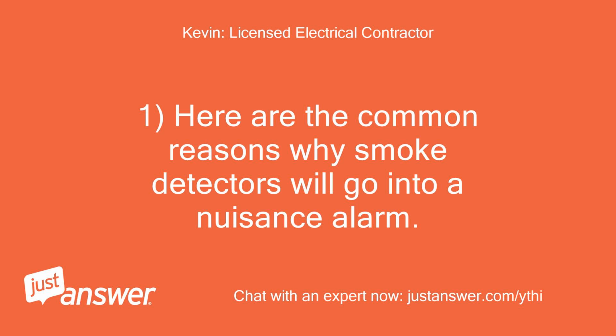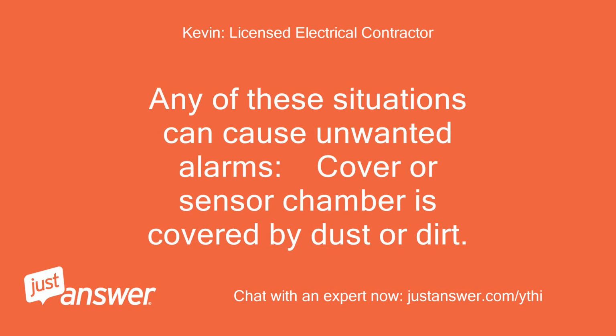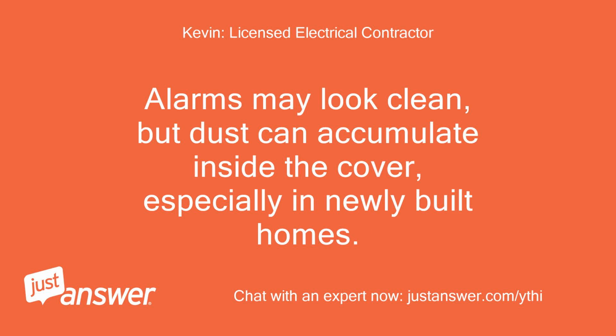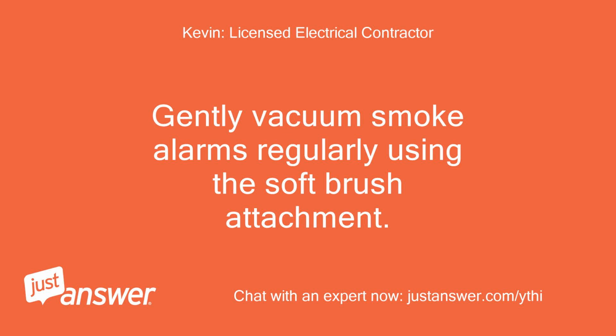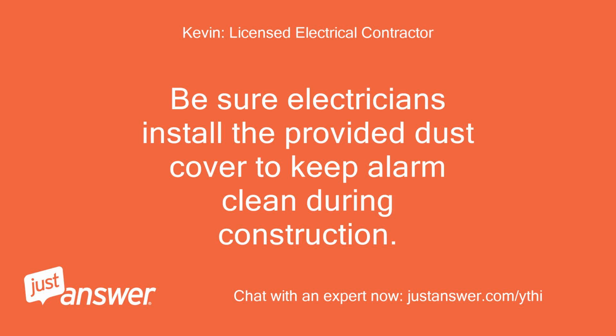1. Here are the common reasons why smoke detectors will go into a nuisance alarm. Any of these situations can cause unwanted alarms. Cover or sensor chamber is covered by dust or dirt. Alarms may look clean, but dust can accumulate inside the cover, especially in newly built homes. Gently vacuum smoke alarms regularly using the soft brush attachment. Be sure electricians install the provided dust cover to keep alarm clean during construction.